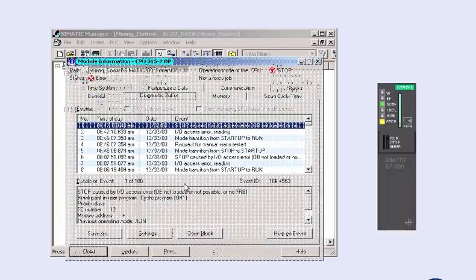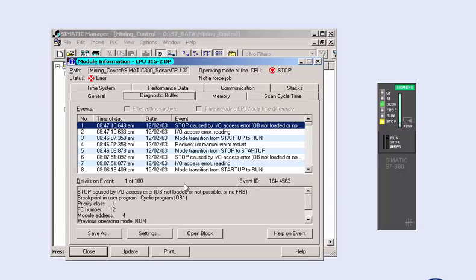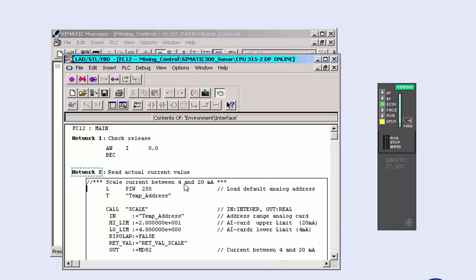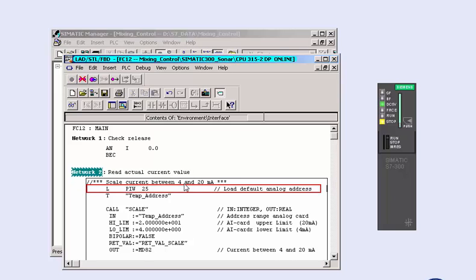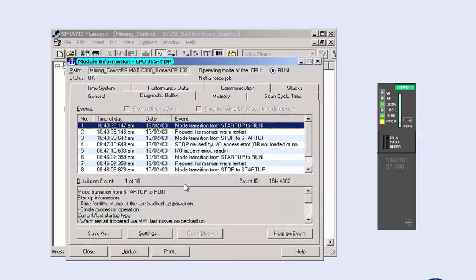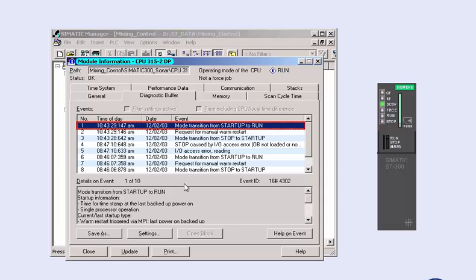If, as in our next example, the error is caused by the user program — for example, access to a non-existing module address — then you can jump directly to the faulty block. The diagnostic buffer thus enables you to directly and effectively find the error and remove it. The stop cause of the faulty I/O access is directly removed in the block online, so that after restart, the CPU is now in run mode and runs without errors.